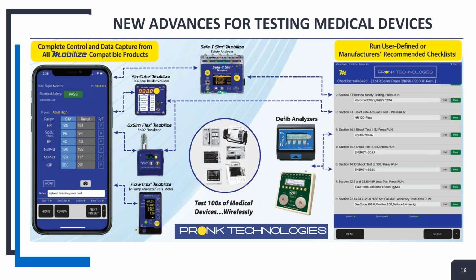5.1. And what's our tolerance? Yeah, so it allows us to know what our pass-fail range is. You get your result right there. Hit pass, and done. Go on to the next test. So that's the general idea behind it, to give you that guide. We'll do one more discharge test so you can see it.